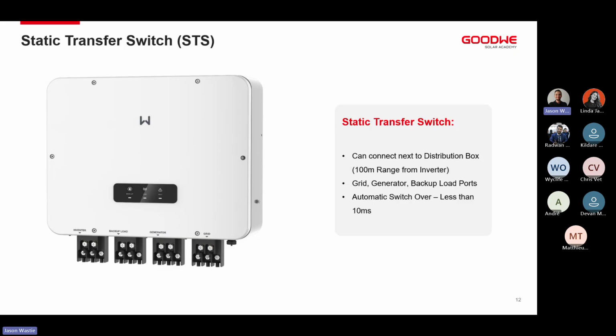So if we're looking at a site, for example, that is a filling station, we'll use a filling station as an example because they generally have it already installed in this way. In the corner of the property, you'll have your main incomer, your utility incoming, and then you'll have your big diesel generator connected there. You'll have an ATS from there running into the main building, and you'll have one cable existing running into that main building. That cable that's running from your ATS or from where your generator and main incomer are coming in to your main building is generally a much bigger cable, and it is quite expensive to really run underground and.